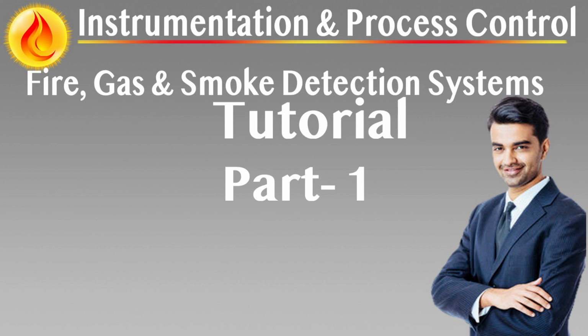Open path gas detectors, extended coverage and perimeter defense for flammable gas detection. Open path gas detectors, also referred to as line of sight, LOS detectors, provide continuous volumetric monitoring of hydrocarbon gas concentrations along a defined optical beam path. Unlike point detectors that monitor a single location, open path systems detect gas anywhere along their transmission path, making them ideal for perimeter monitoring, open process areas, and detection of gas cloud migration.